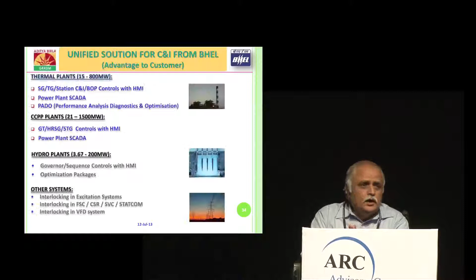And other features we've been talking about, like condition monitoring and so on—since this is a small plant, those things could not be fully adapted as the requirements are not so high. But to some extent, we have done condition monitoring, alarm trend analysis, even of vibration signals, as part of the DCS trending. This is our experience.